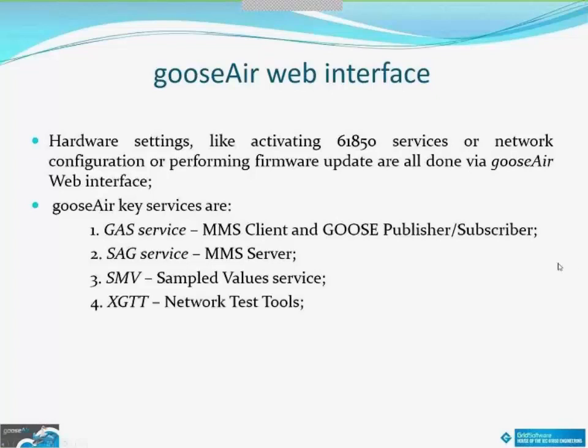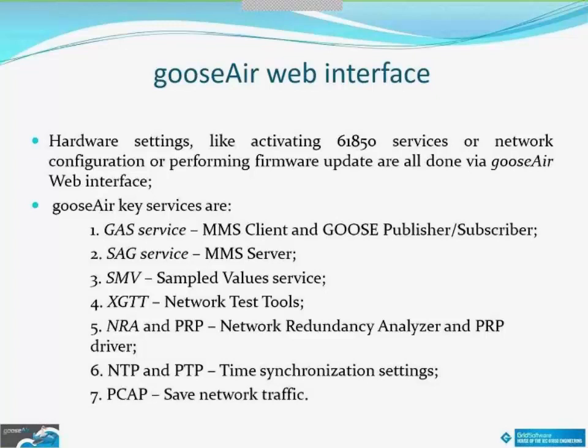XGTT service is used for testing and measuring of network performance using various network test tools. Then we have Network Redundancy Analyzer and PRP Driver, which allow GooseAir to engage in PRP network environment, both as a tool for monitoring PRP traffic as well as for simulating GOOSE messages with PRP trailer. GooseAir can also be synchronized either by NTP or PTP protocol. And in the end, GooseAir offers also PCAP service, which allows users to save network traffic on one or more GooseAir interfaces.